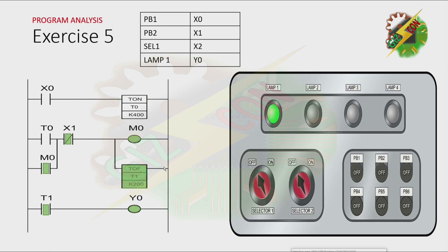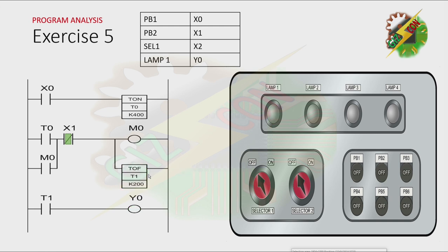Now let's release PB1. As you can see, even if we release PB1, the lamp is still on because there is a latching here. The only way to turn it off is by energizing X1. Now let's press PB2. Because PB2 is pressed, X1 here will open, and that will cause M0 to be deactivated. Because there is no signal here anymore, the timer will start counting. After 2 seconds, the timer is deactivated, and that will cause this contact to go back to its initial state. Because of that, Y0 will be de-energized and the lamp will turn off.